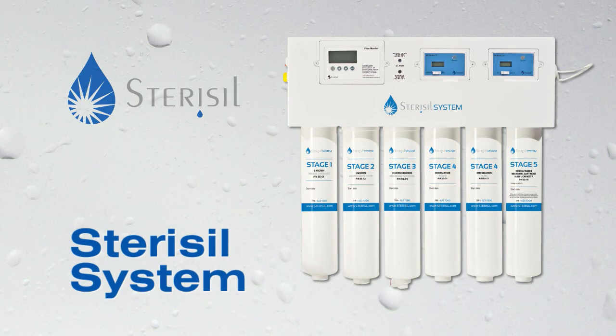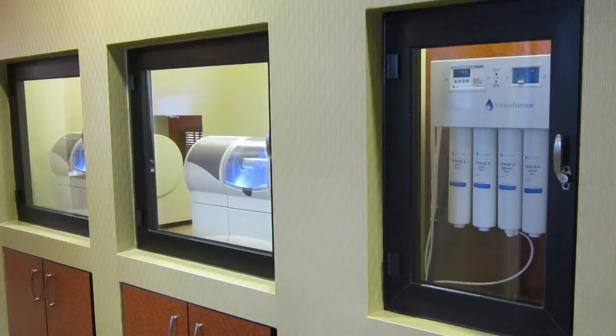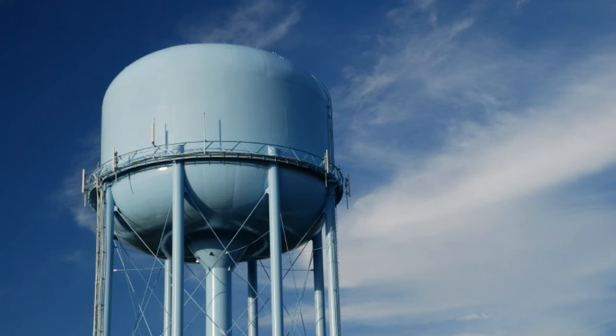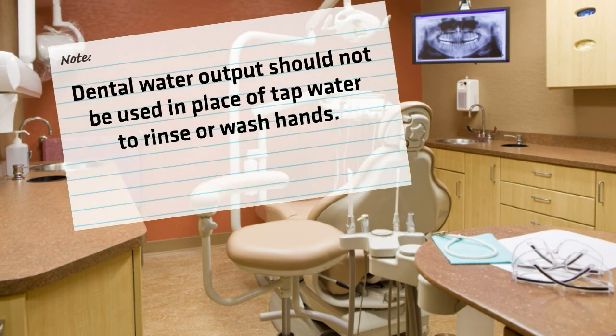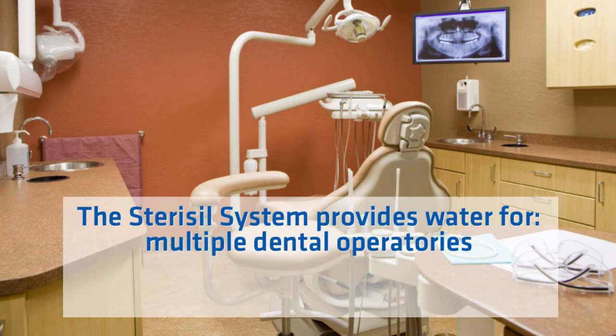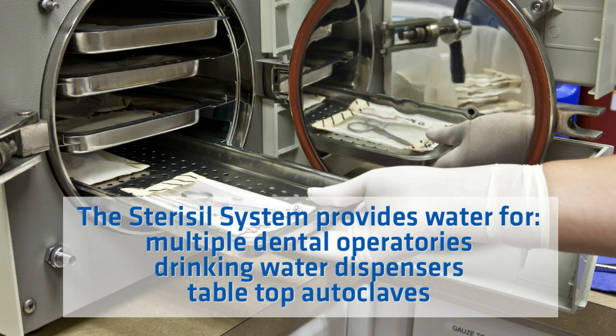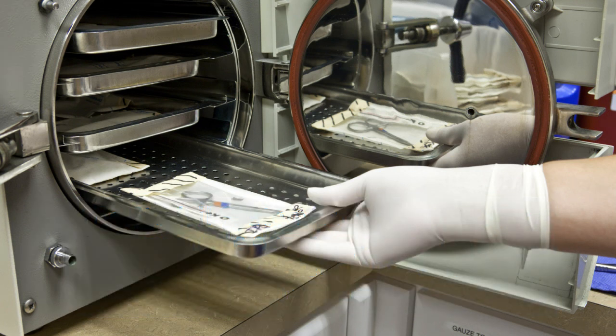The Sterisil system is engineered to provide distilled quality autoclave water and treated dental water. It is a wall or cabinet mounted point-of-entry water purification system designed to easily connect to the municipal water supply. The system is intended to directly feed only to dedicated lines to each dental chair, and not intended for distribution to sinks, toilets, etc. The Sterisil system provides water for multiple dental operatories, drinking water dispensers, and tabletop autoclaves.